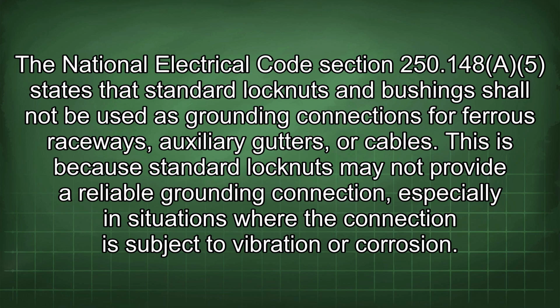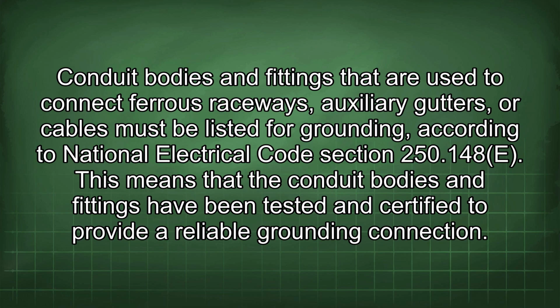250.148 states that standard locknuts and bushings shall not be used as grounding connections for ferrous raceways, auxiliary gutters, or cables. This is because standard locknuts may not provide a reliable grounding connection, especially in situations where the connection is subject to vibration or corrosion. Conduit bodies and fittings that are used to connect ferrous raceways, auxiliary gutters, or cables must be listed for grounding according to National Electrical Code Section 250.148. This means that the conduit bodies and fittings have been tested and certified to provide a reliable grounding connection.